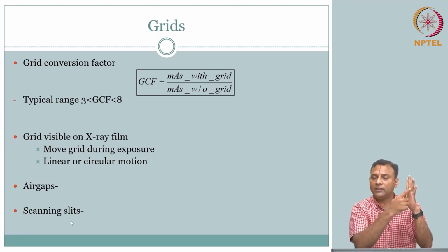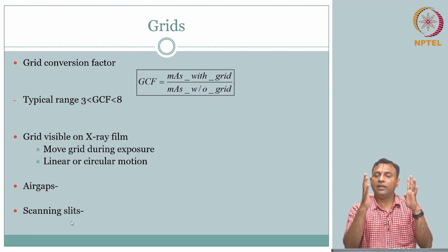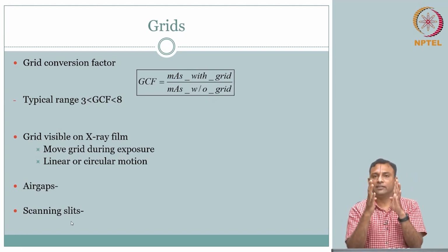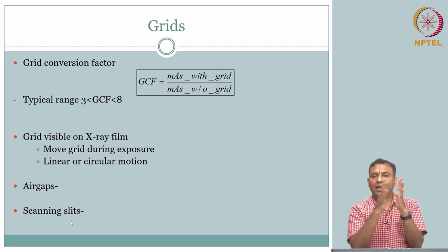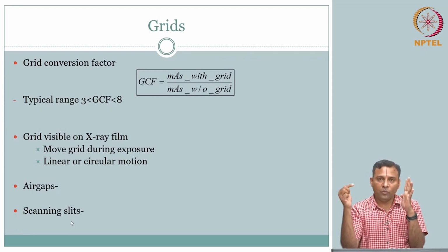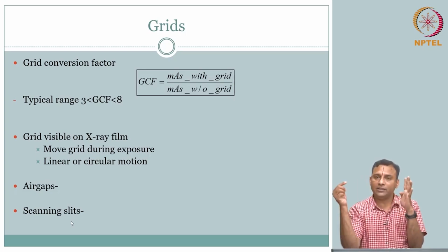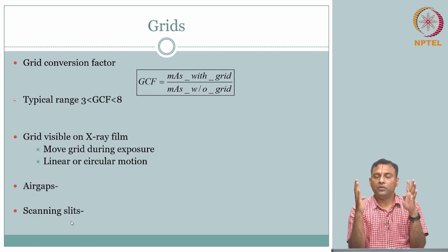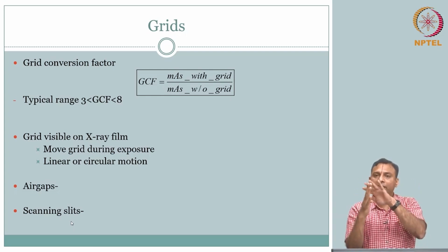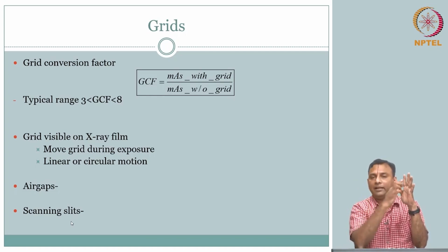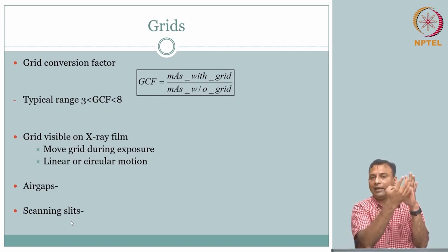Instead, what we can do is have the slit also at the beginning. That way you don't even dose the patient where the grid is. So you align these two perfectly. That way only through the transparent locations in between the slits is the signal going through. Every other angle, even here, it is arrested, and therefore whatever comes out of Compton scattering you can manipulate here and it can get arrested.